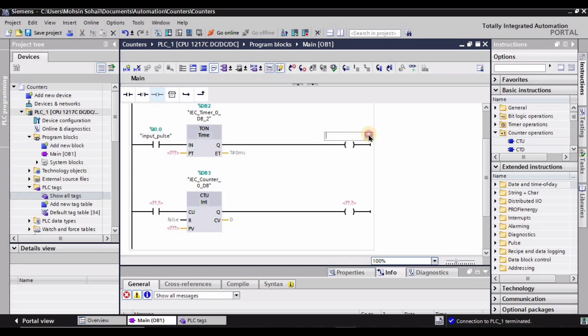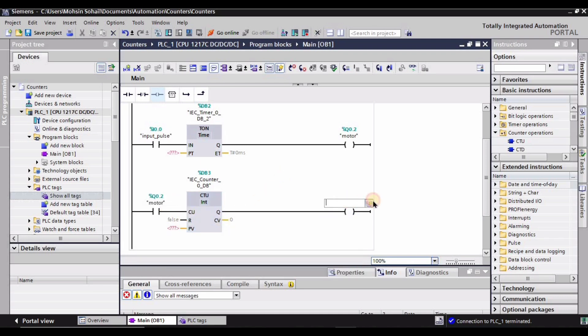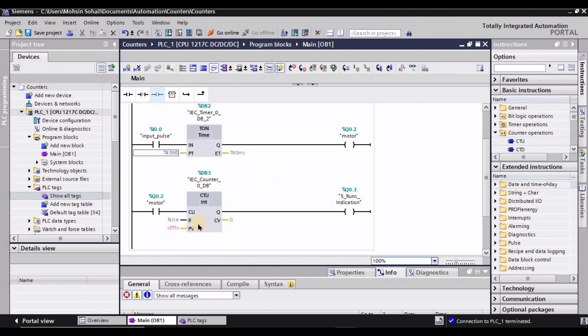This right here is the input pulse tag. When the motor turns on we want a pulse given to the counter as well, so I'm assigning this normally open contact the same address as the motor. This is going to be our five-runs indicator. Now let's assign the preset time — and intentionally I'm going to make a mistake here: I've written three milliseconds instead of 3000, because time in TIA Portal is in milliseconds, so 3000 is needed for three seconds.